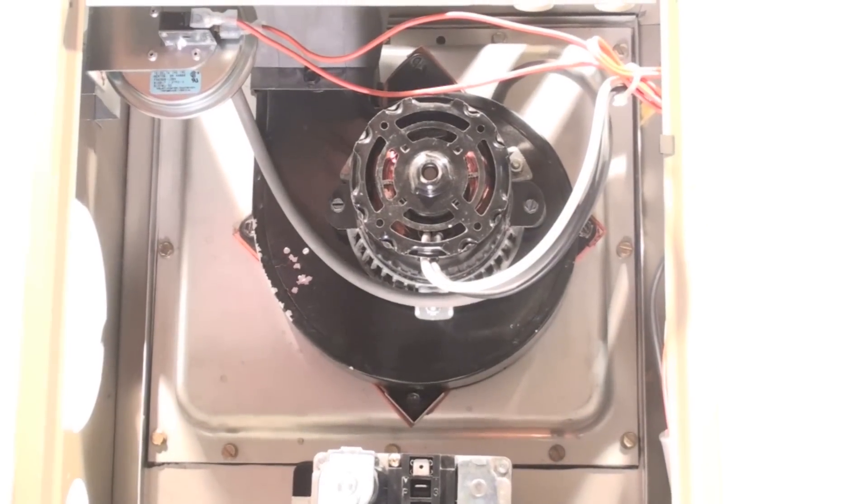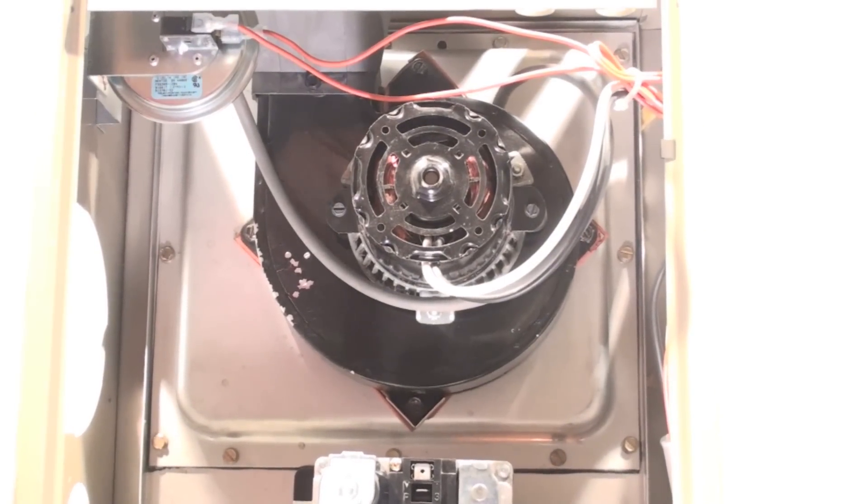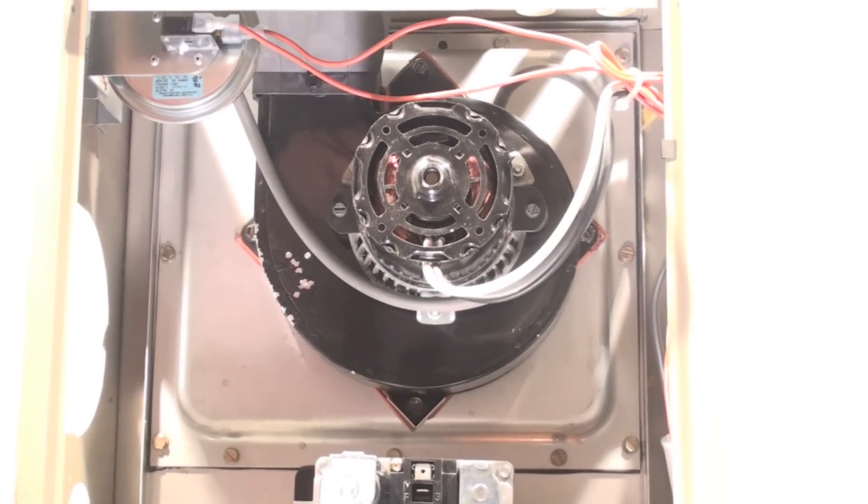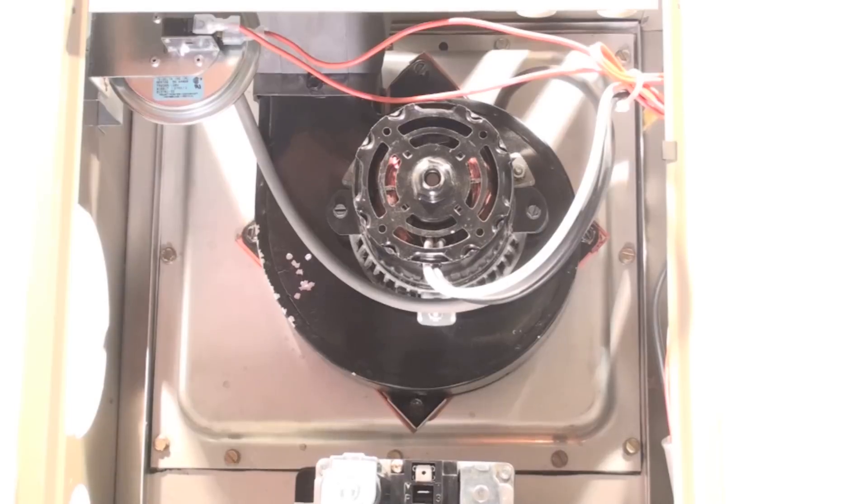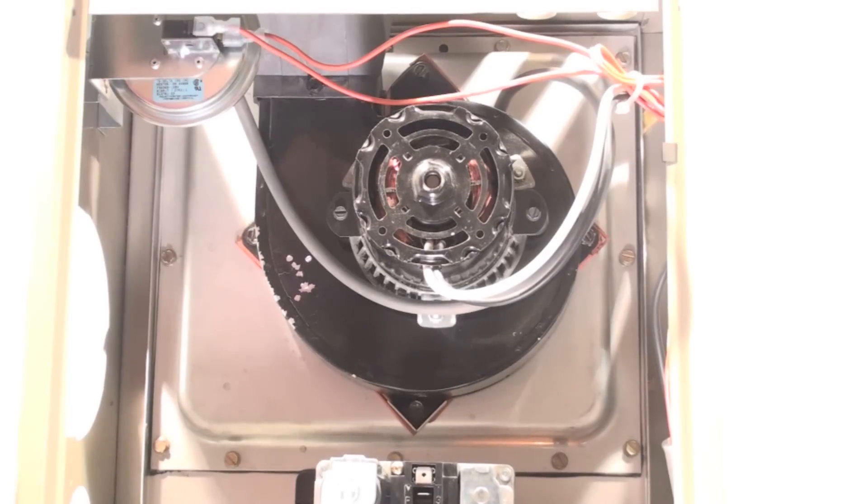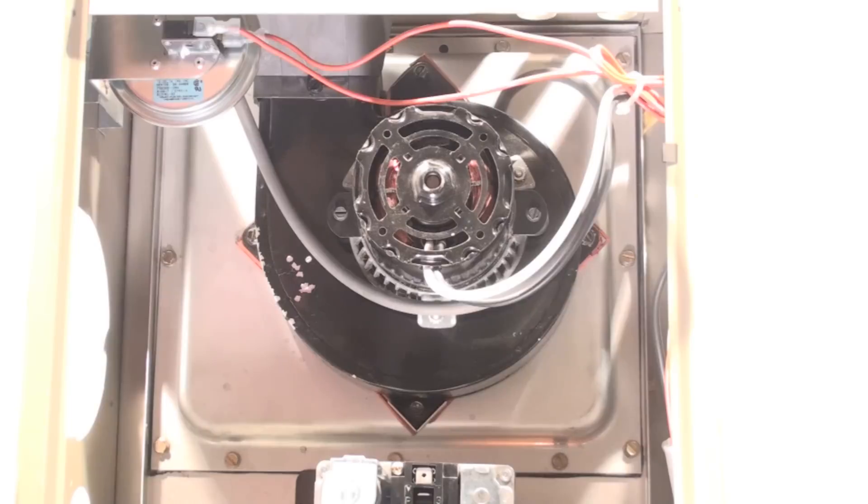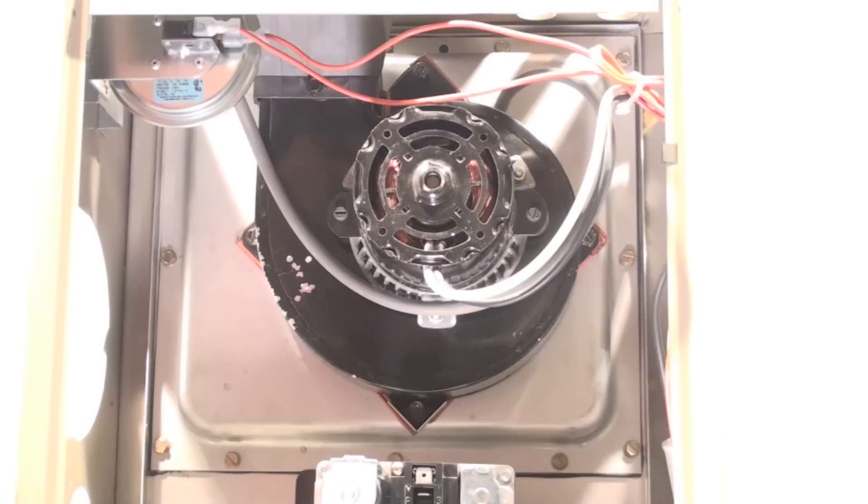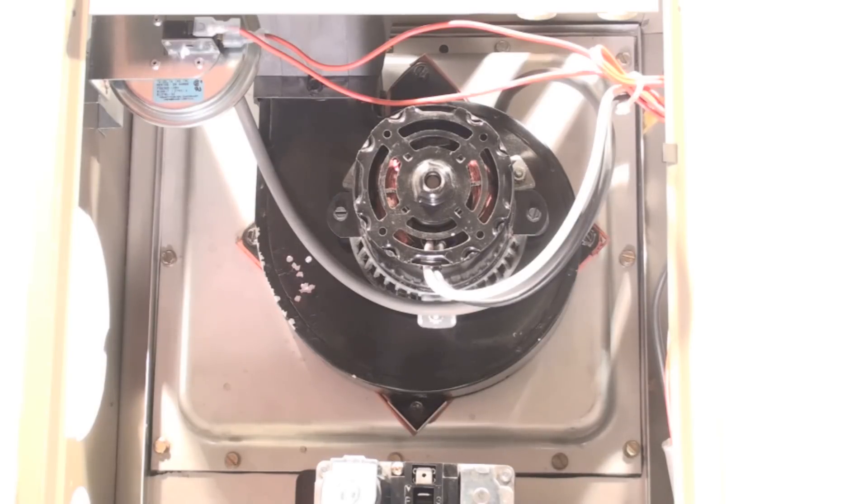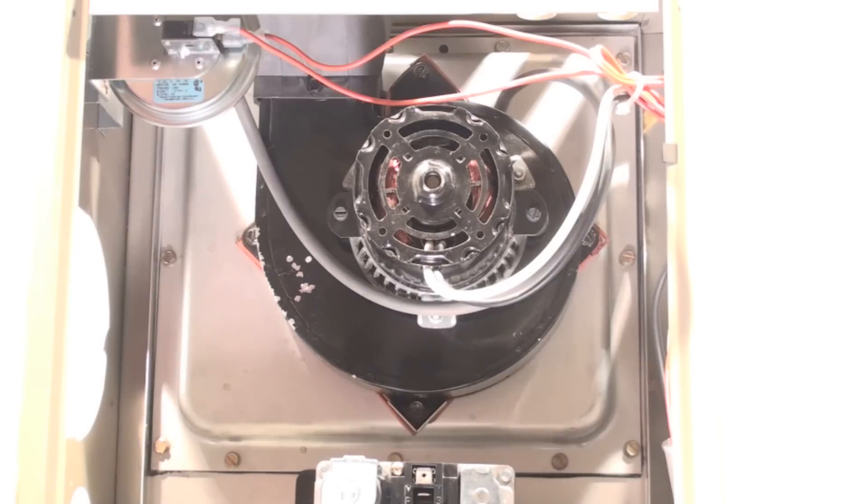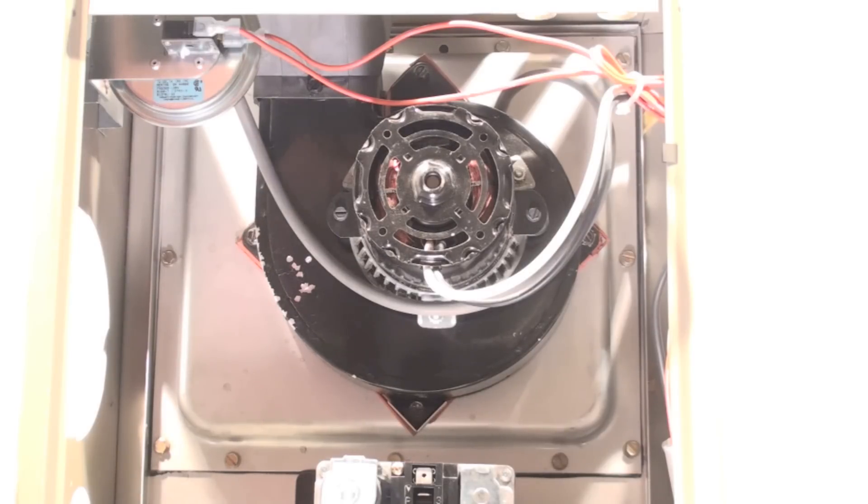But if it's open, it will go ahead and say 'Okay, I got an open pressure switch' and start the inducer. The inducer will start, and then the pressure switch closes. That's going to allow the unit to get started on its sequence to light off the burner.